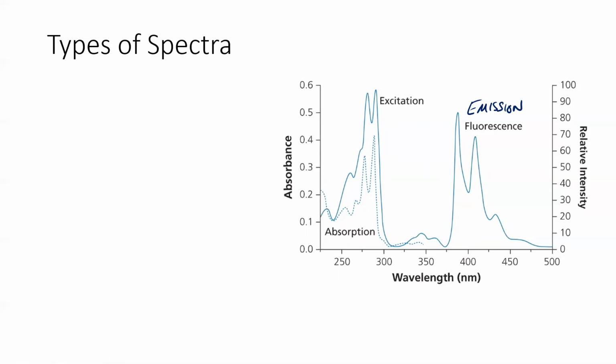So you can take excitation spectra, fluorescence or emission spectra, and then absorption spectra, only if we have a way to bypass that first monochromator, right? We need all wavelengths of light in order for us to do that. Or you can have your monochromators track, so they're both on exactly the same wavelength as you go through the scan to get absorption.